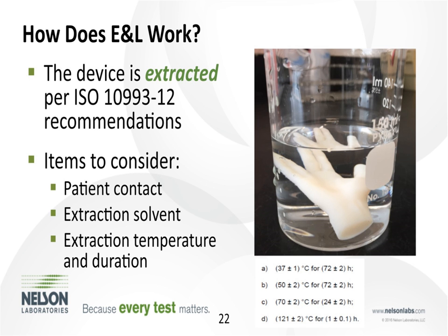What you need to consider when extracting your device is what the patient contact of the device is, what extraction solvents should be used, and what extraction temperature and duration you should use. For typical prolonged or permanent contacting devices, we're commonly seeing a recommendation of 50 degrees Celsius for a 72-hour extraction.